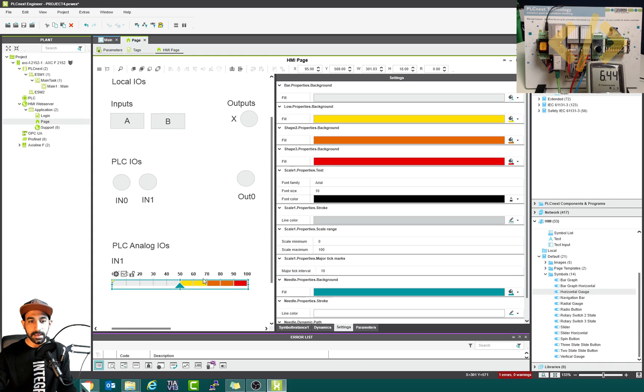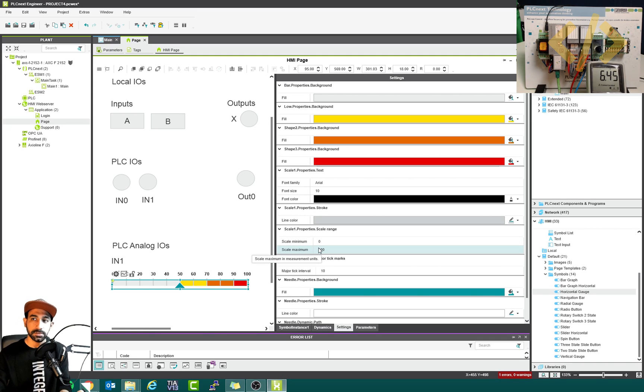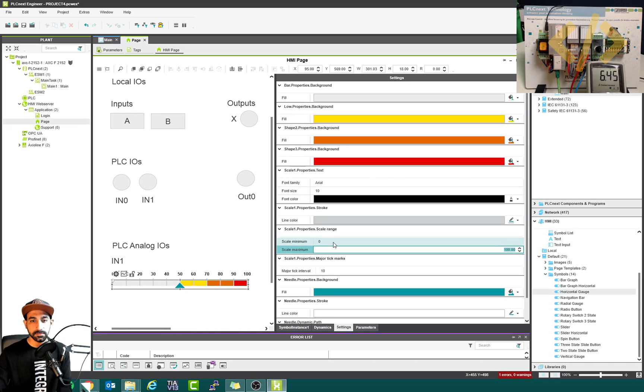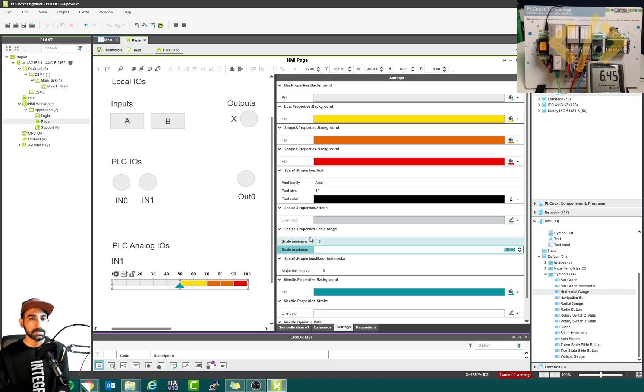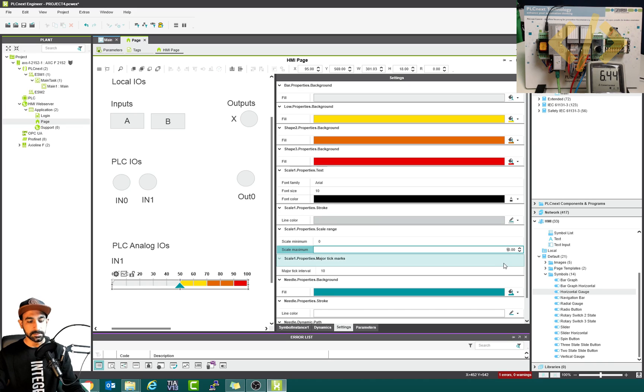If you want to show it as a voltage, I can change this to zero to ten volts. It totally depends on what you want to see. If you want to see it as a percentage, use zero to 100. If you have a motor speed going to a VFD with a frequency of zero to 50 or zero to 60 Hz, you can define whatever scale you want. In this example, I'll take 10.